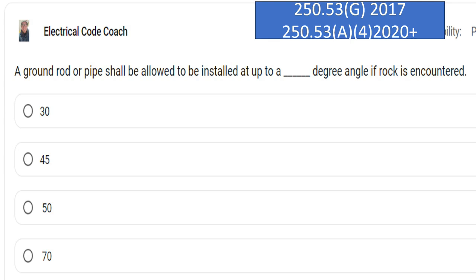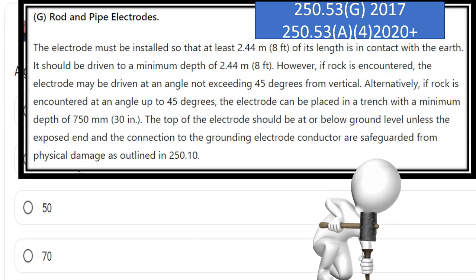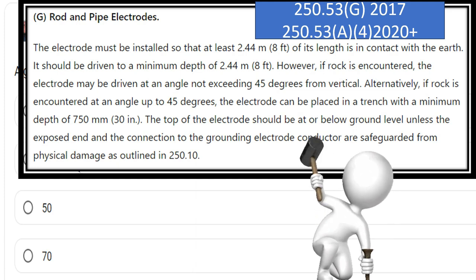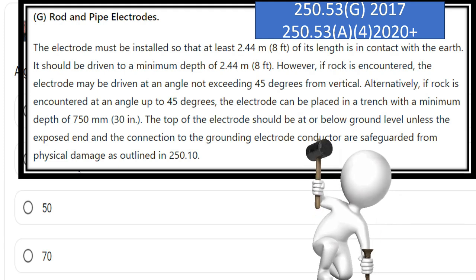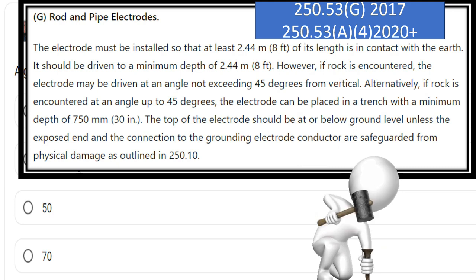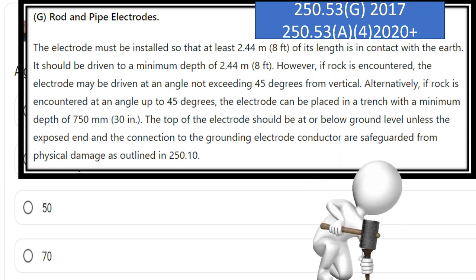A ground rod or pipe shall be allowed to be installed at up to a blank degree angle if rock is encountered. The correct answer is 45 degrees. The electrode must be installed so that at least eight feet of its length is in contact with the earth — it should be driven to a minimum depth of eight feet. However, if rock is encountered, the electrode may be driven at an angle not to exceed 45 degrees from vertical. Alternatively, if rock is encountered even at up to 45 degrees, the electrode can be placed in a trench with a minimum depth of 30 inches. The top of the electrode should be at or below ground level unless the exposed end and connection to the grounding electrode conductor are safeguarded from physical damage as outlined in 250.10.